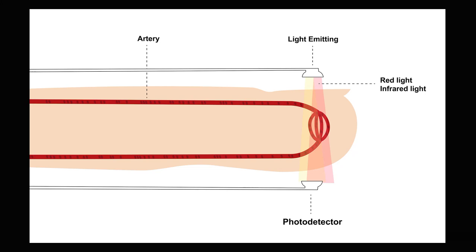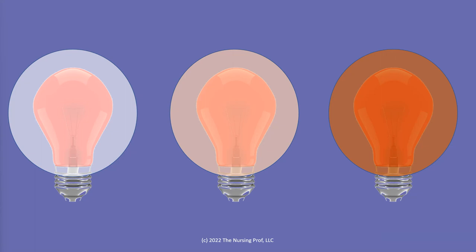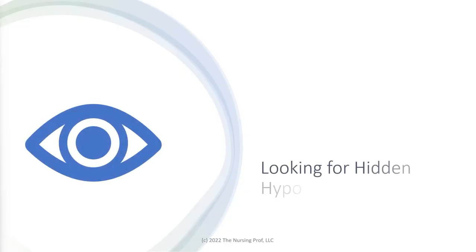Now let's take a look at how our pulse oximeter may be affected in different patient populations. If we're assuming we have a red light here and a fairly light-skinned patient, then we would anticipate we could still see that reddish light coming through the skin. However, as we change the pigmentation, the color of that red starts to change. Even darker yet, the color is changing even more with that pigmentation. What this does is it confuses our pulse ox, and it is not able to pick up a very accurate reading of the patient's oxygen level in the bloodstream.